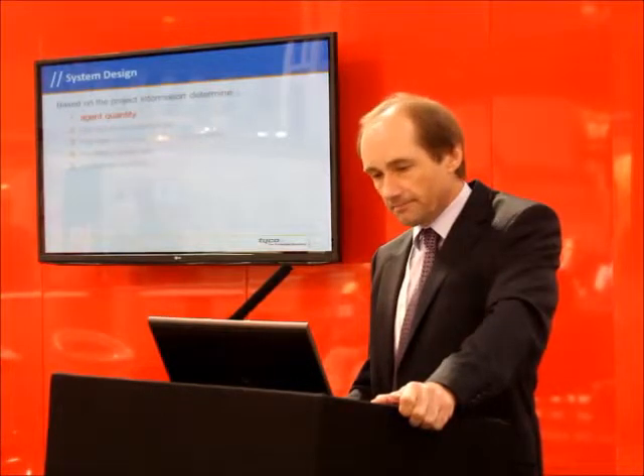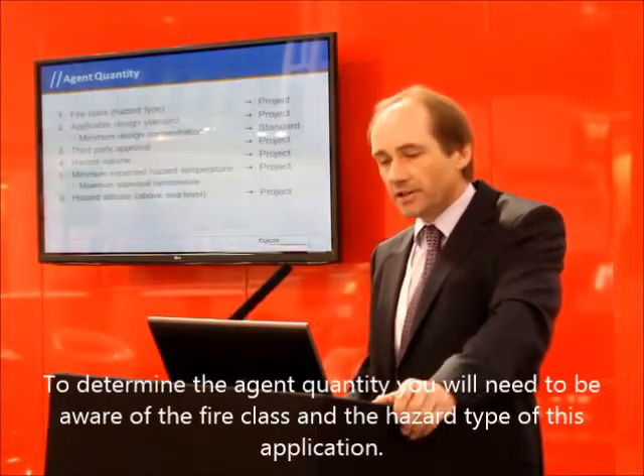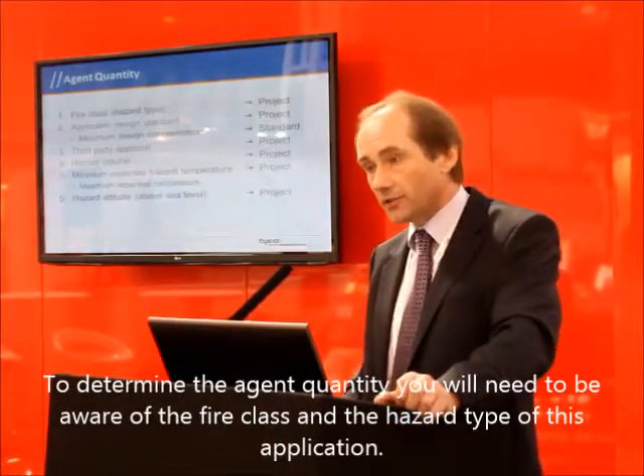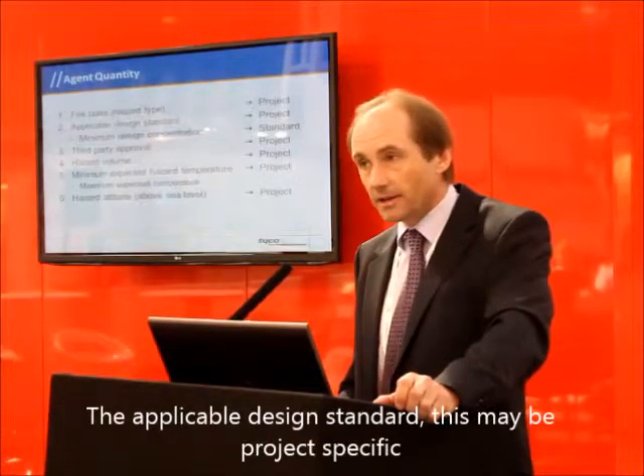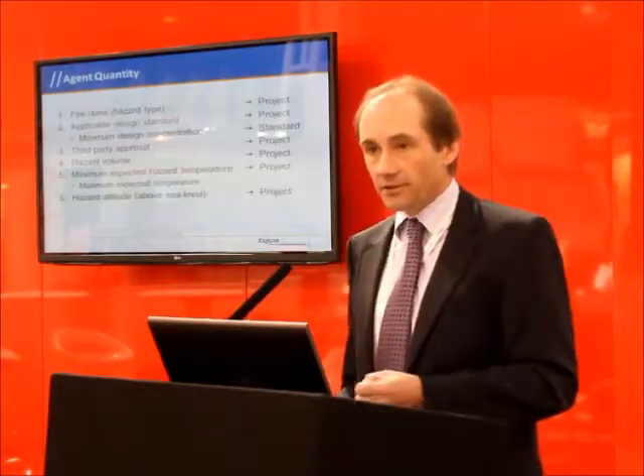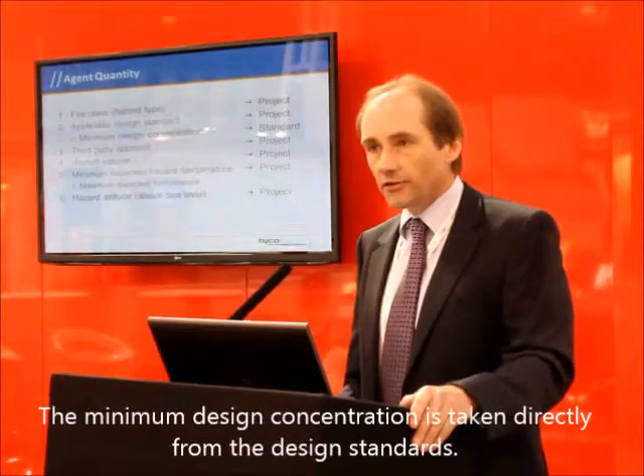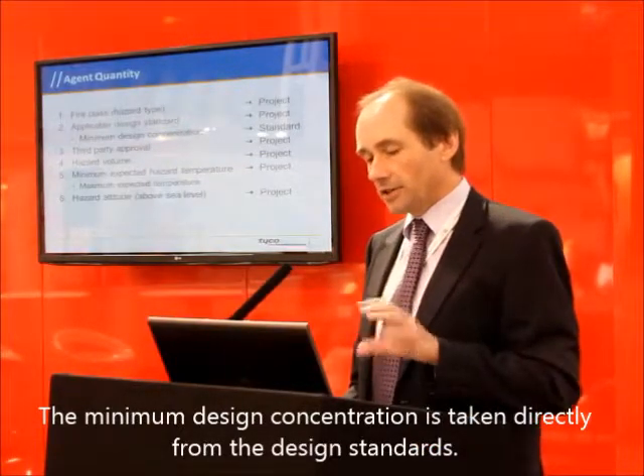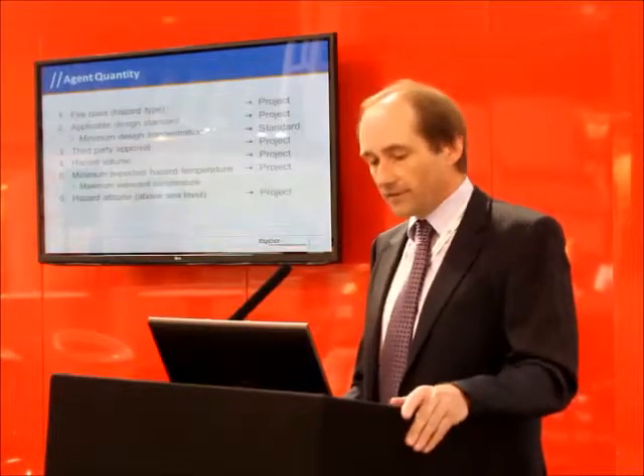Looking first at the agent quantity, for this you will need very specific project information: what is the fire class and the hazard type that we are dealing with in this particular application. The applicable design standard — again, that may well be project specific. Typically if it's a system in the UK it will be designed according to BS EN 15004, but that isn't always the case. The minimum design concentration is taken directly from the design standards — if it's a system in the UK, that concentration can be established from BS EN 15004.